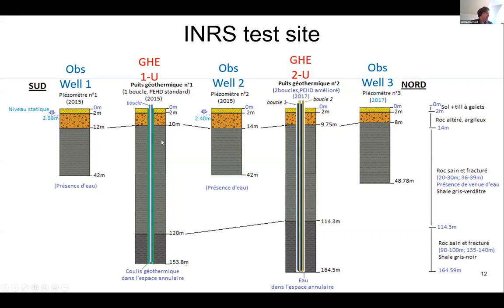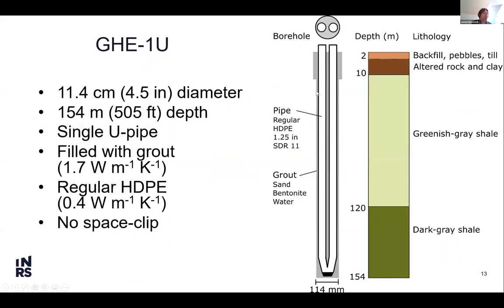One of the holes is a single U-pipe versus this one, a double U-pipe, a little bit deeper, 160 meters versus 153 meters. The ground heat exchanger with the single U-pipe was installed as a first research test. We wanted to verify the impact of a borehole with a smaller diameter. Here it's not 6-inch but 4.5 inch, so 114 millimeters in diameter. A drilling contractor came on site and proposed this borehole with a smaller diameter, and we wanted to see the effect on the borehole thermal resistance.